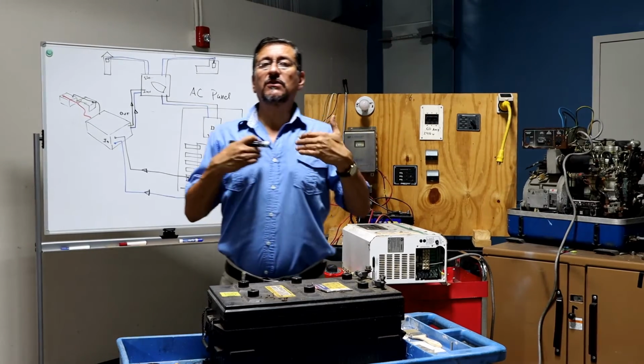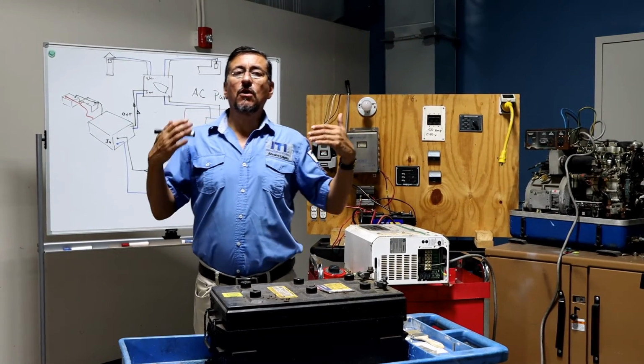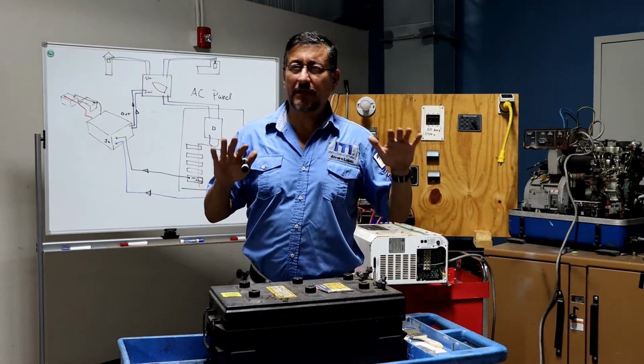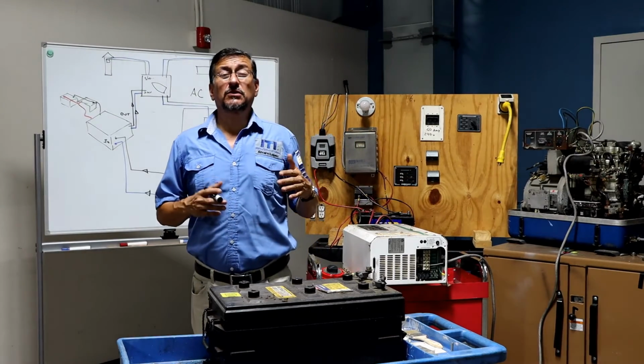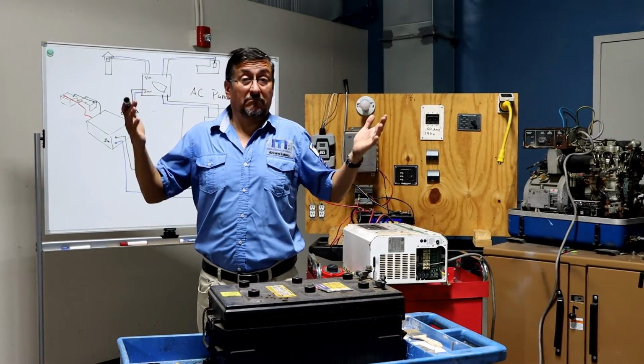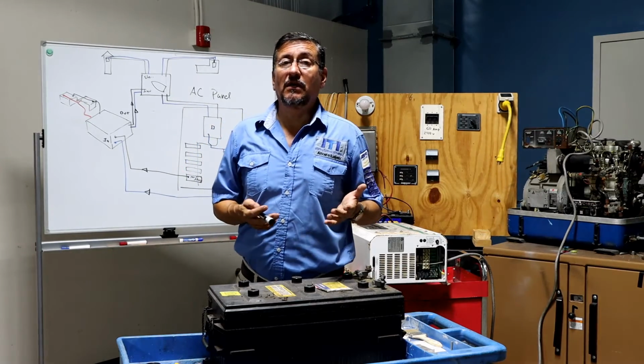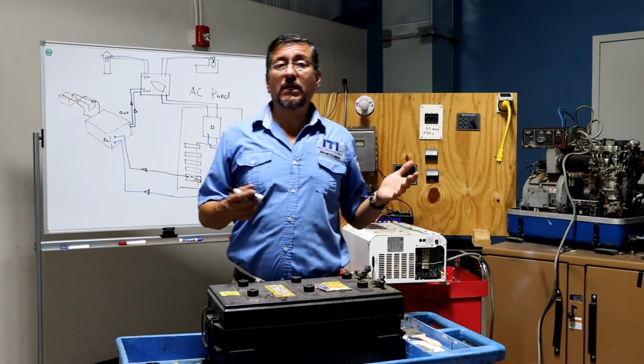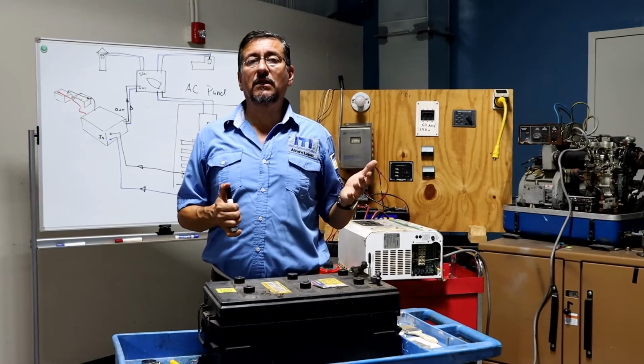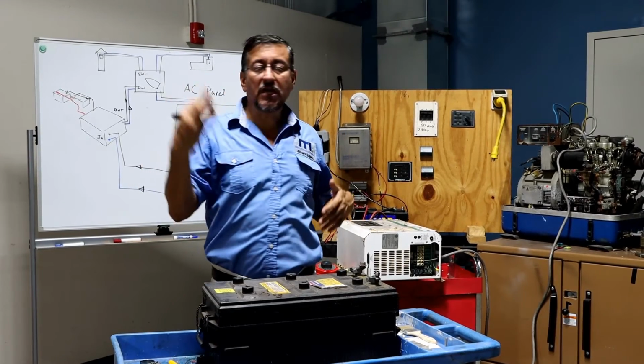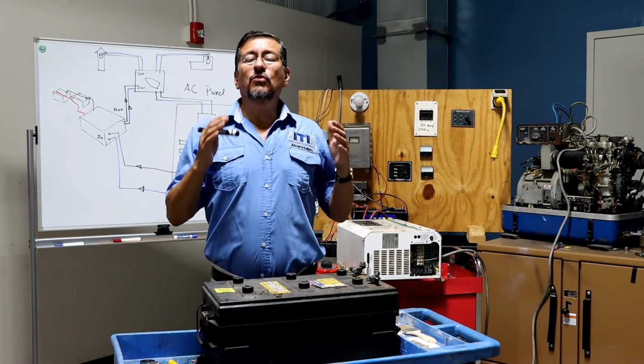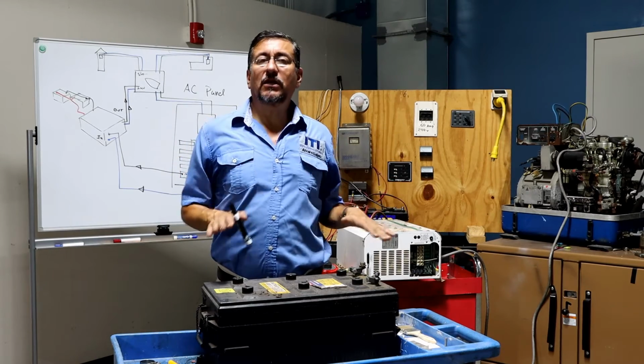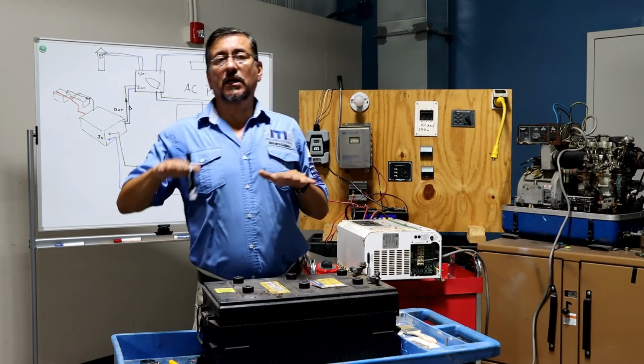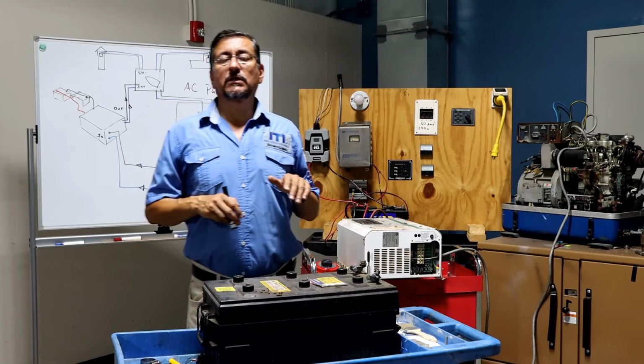My recommendation is to never run a generator more than 8 hours, 10 hours maximum, because the generator is a diesel engine or gasoline engine. Running the engine more than 8 hours is not good for the engine. It doesn't matter if the oil is synthetic and the refrigeration is good. You need to stop the generator, let it rest, and run another generator for another 8 hours.